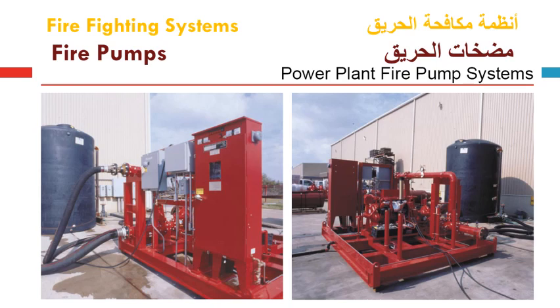This slide also continues how we can install the skid discussed in the previous slide at an outdoor location, in power plants or in factories where we don't have a location for a fire pump, and we can install it outdoors, and the tank will be located here. This is a suction tank which will provide the fire water required through this hose system to connect the suction line during operation, and also through the discharge line we can return this water to the tank during the testing process for this pump.